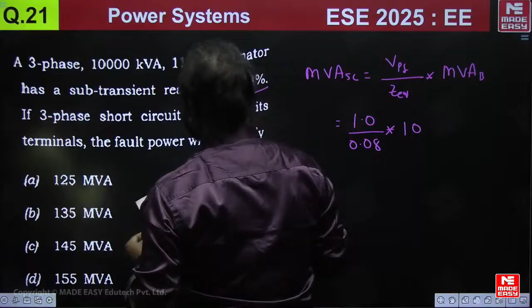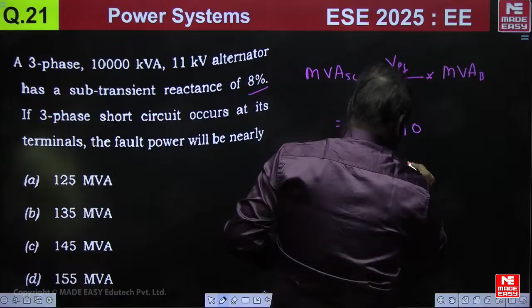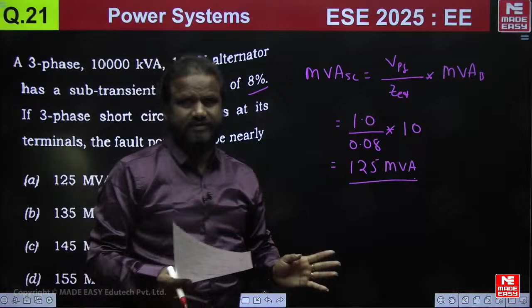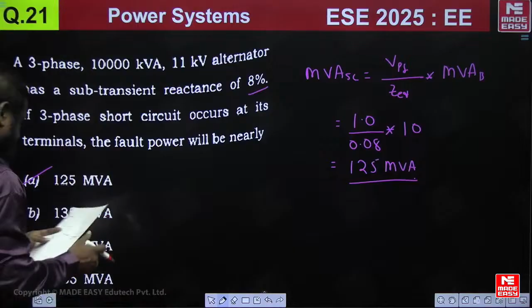Here the subtransient reactance has been given as 8%. So 0.08 into the base value, which you have to take as the rated value, that is 10000 kVA, equivalent to 10 MVA. So the fraction is 12.5, and 12.5 into 10, that is equal to 125 MVA. Normally the subtransient reactance is in the range of 8% to 15%, so you have to observe that. Therefore your answer is A. This is a simple calculation.